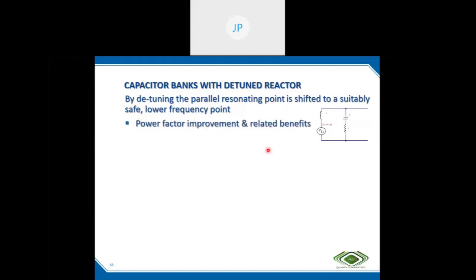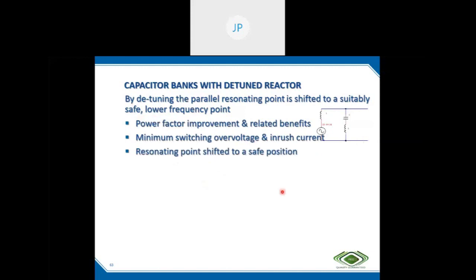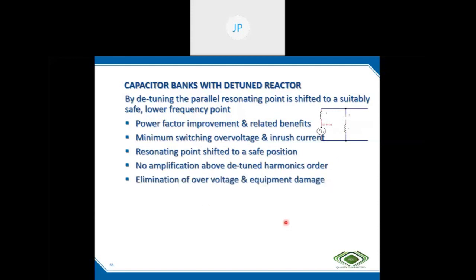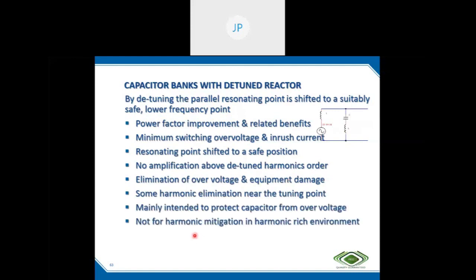Power factor improvement and related benefits will be there. Minimum switching overvoltage and switching inrush current. The resonating point is shifted to a safe position. No amplification above the detuned harmonic order. Elimination of overvoltage and equipment damage. Some harmonic elimination near the detuning point, but it is mainly intended to protect the capacitor, not for harmonic mitigation in a harmonic rich environment, because not much harmonic elimination will be there.